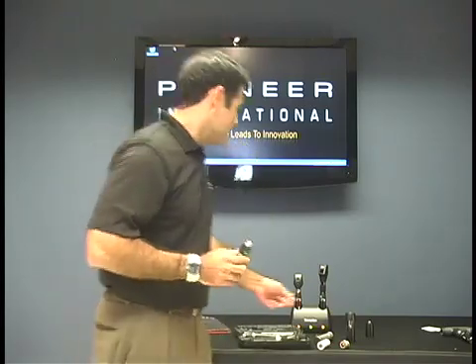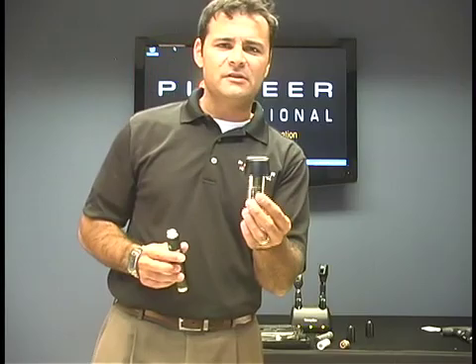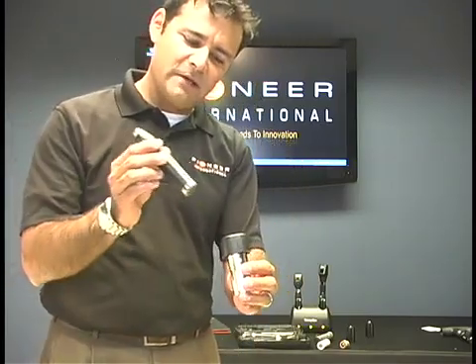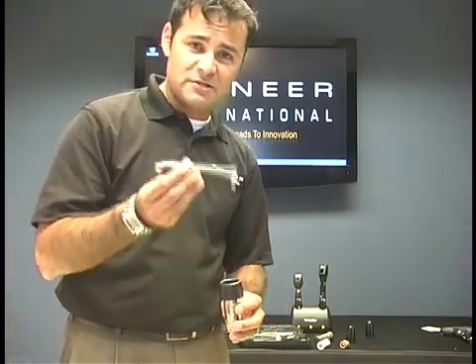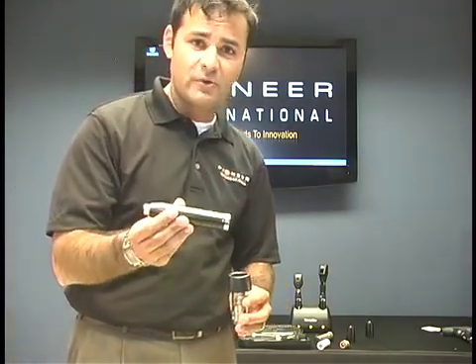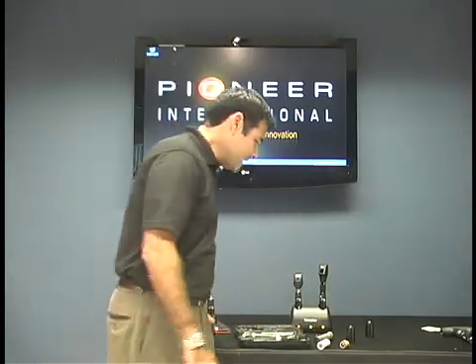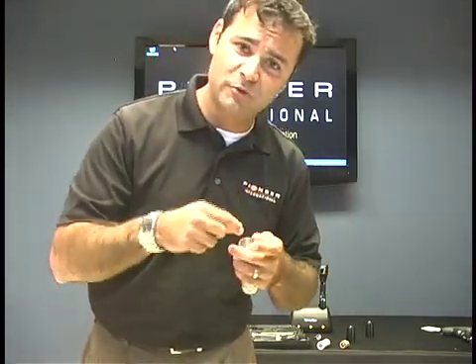What's also nice is that this unit comes with what's called a wall adapter, which fits in the lane you'll be working in and allows you to charge the handle in the future. So although you're investing in it now, it will work for you later on. The silver NiCad handle could also charge, but you'd have to go grab it, unplug it from the wall, screw it on, and then put your ophthalmoscope on — and you're not going to do that. Trust me.